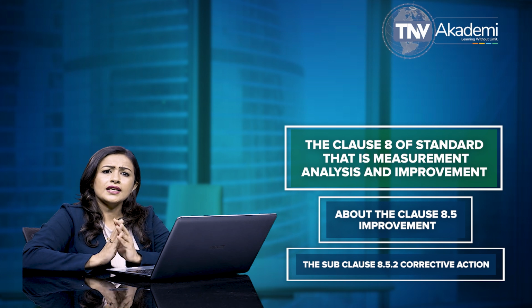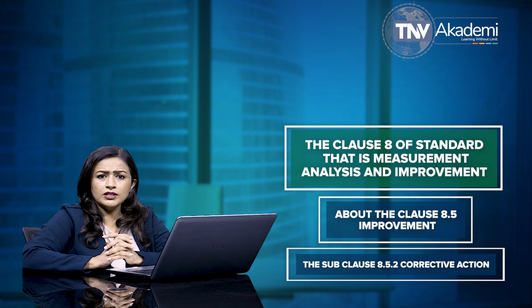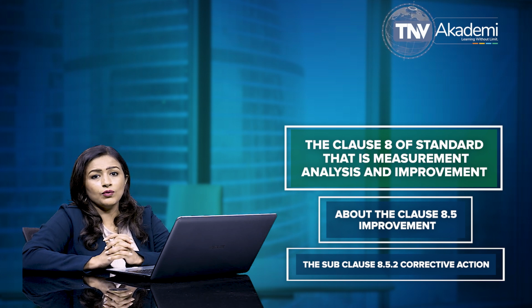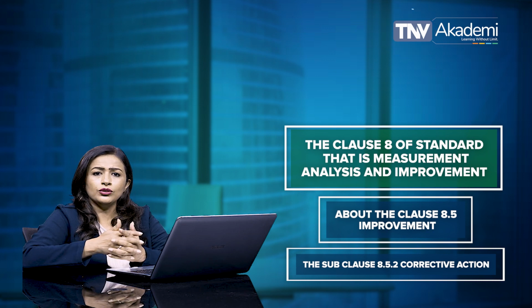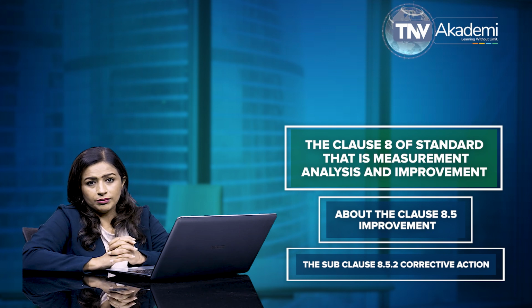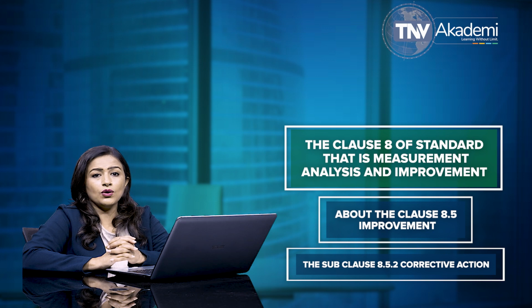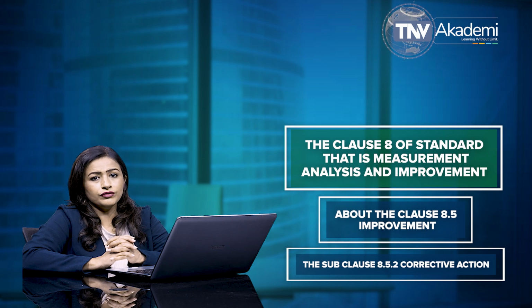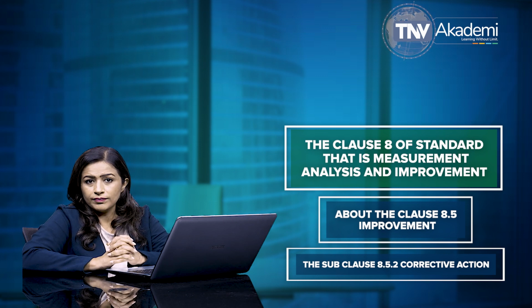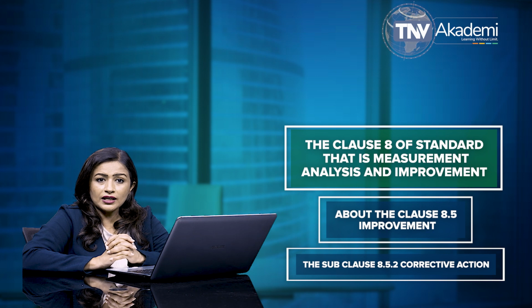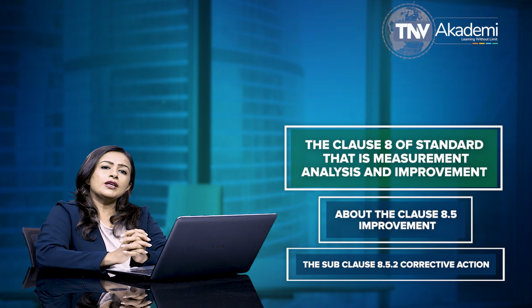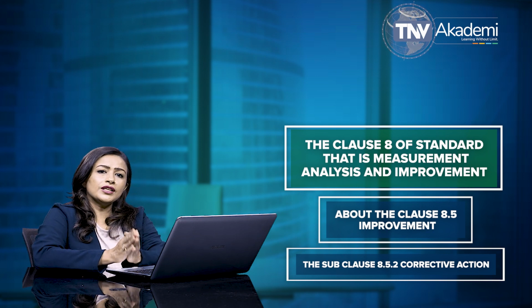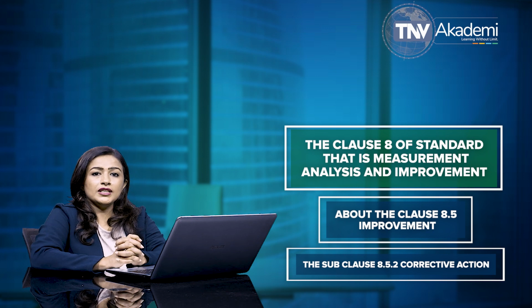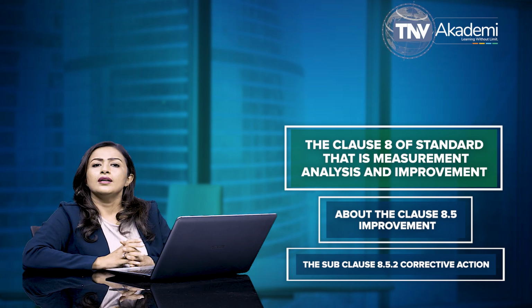This clause says that the organization must document a procedure to define requirements for reviewing nonconformities, including complaints, determining the causes of nonconformities, evaluating the need for action to ensure that nonconformities do not recur, planning and documenting action needed, and implementing such action, including, as appropriate, updating documentation.